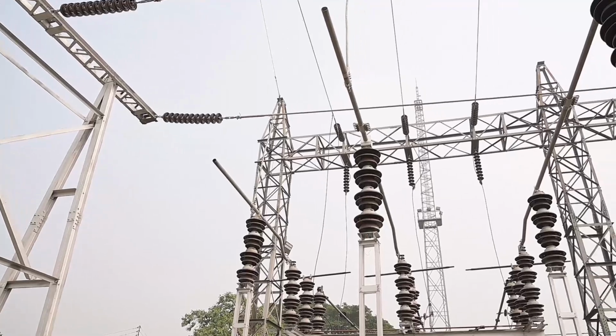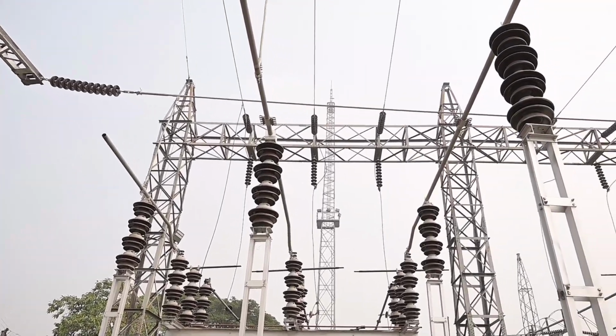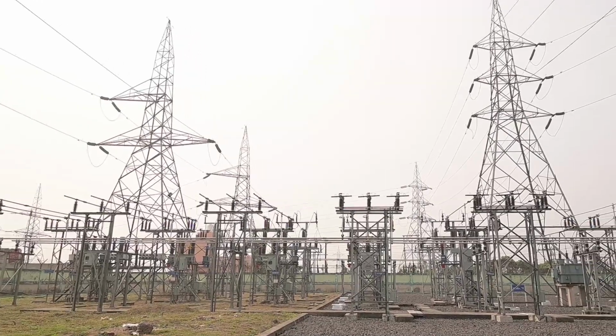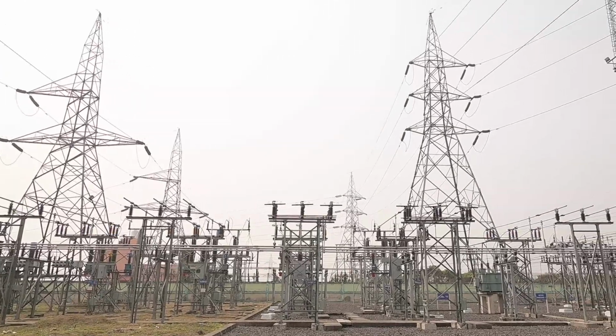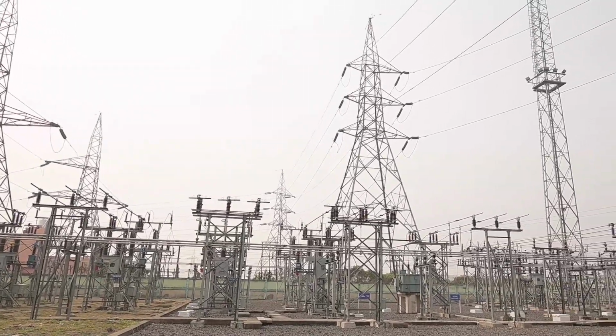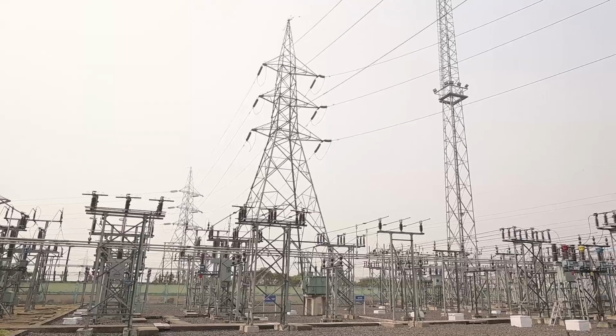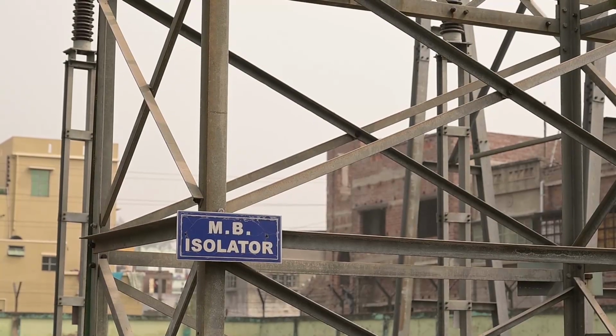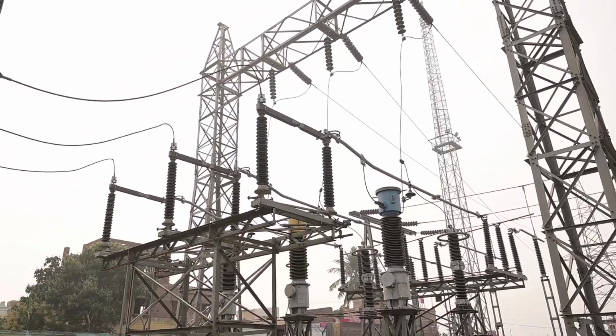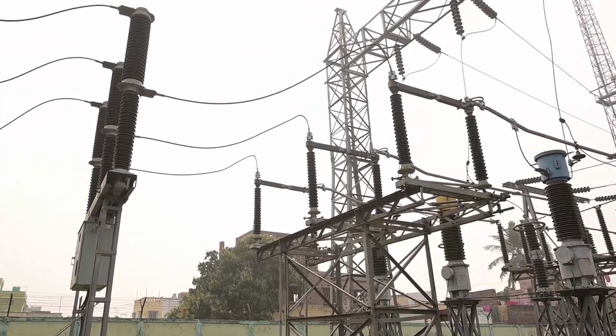We do maintain the proper registers of the maintenance of EHV equipments as well as the battery register of lead acid cell battery as well as the VRLA battery cells. Renovation of the 132 kV and 33 kV system has been done by replacing age-old, trouble-prone and under-capacity isolators to improve system availability, stability and reliability.